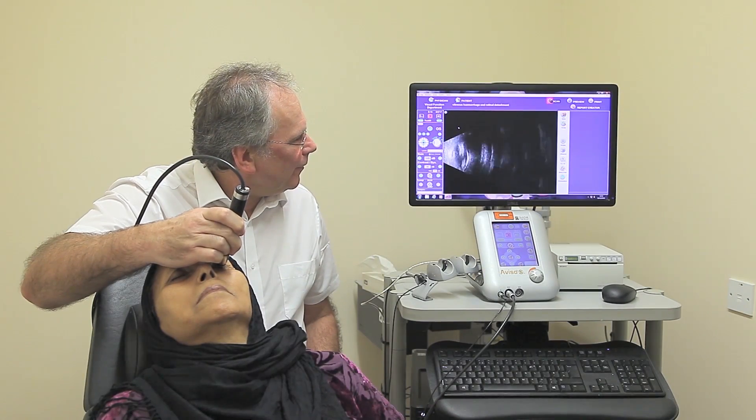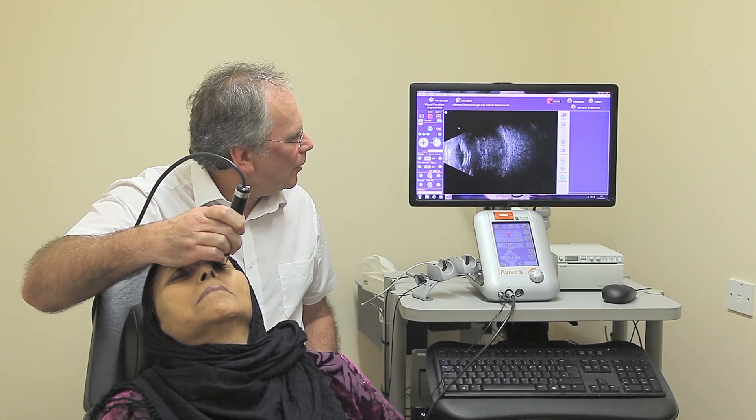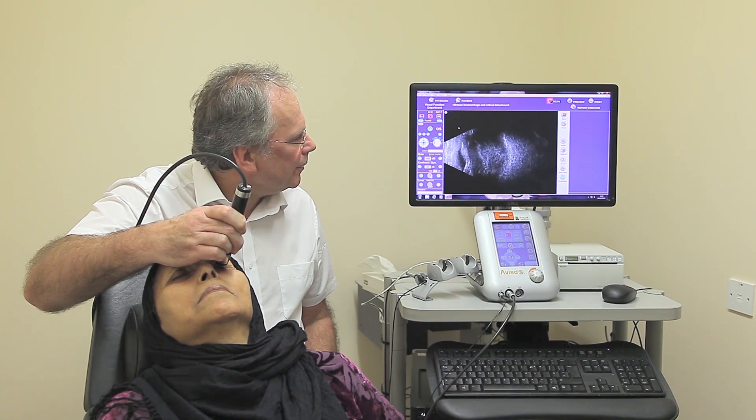The new generation 10 MHz B-probe from Quantel Medical offers unique capabilities of visualising the vitreous, the ocular wall and vitreoretinal structures. One of the major benefits of this new probe is the image quality for the vitreous. With a gain set generally between 100 and 110 decibels, it provides high resolution images of the vitreous, the posterior hyaloid and vitreoretinal relationships such as tractional detachments and tears.